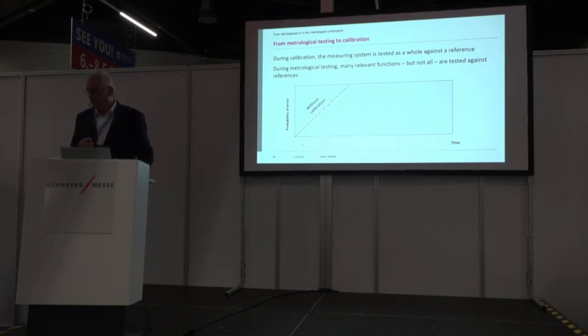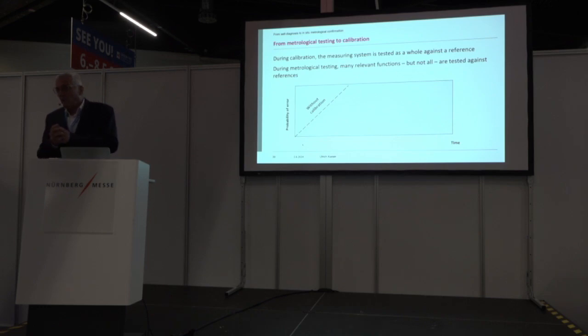You say, okay, after 1 week it's still okay. After 3 months, maybe also okay. After 6 months, I check it better, because the probability is high that the device is out of calibration, out of setting. And for this purpose, you do a calibration.